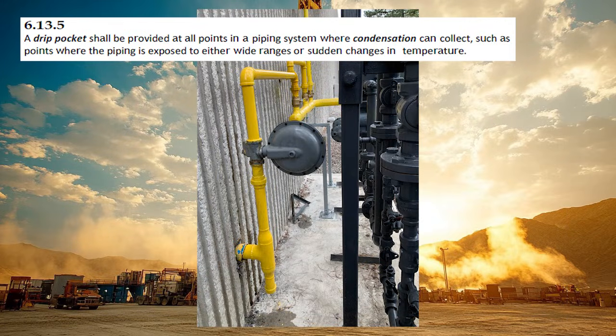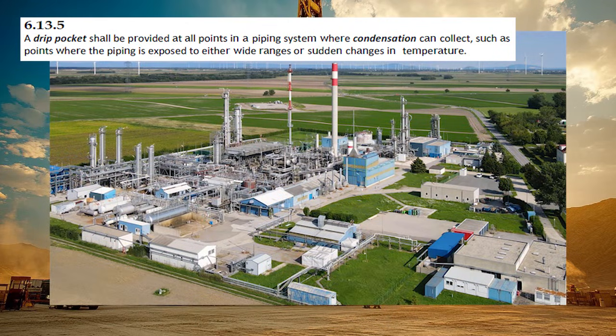Clause 6.13.5 specifically deals with drip pockets. A drip pocket shall be provided at all points in a piping system where condensation can collect, such as points where the piping is exposed to either wide ranges or sudden changes in temperature. I recently spoke with a technician that works for a gas provider, and I asked him when would this condensation occur in the piping, and he let me know this is when a gas provider fails to clean the gas properly. So typically this doesn't happen because generally speaking they're on top of this.